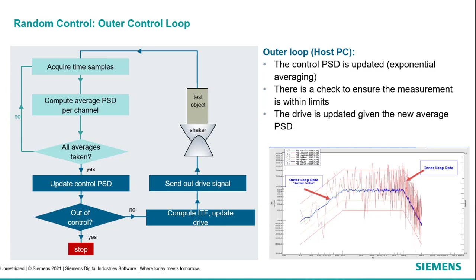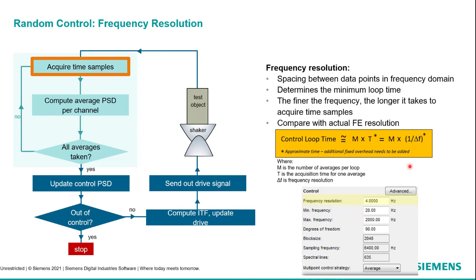Then we have another parameter that is part of the parameter settings, the frequency resolution, and this has a strong influence on the loop time. We have to have at least 1 over delta F for the time of one single average, and then we have a number of averages, and that's going to dictate our control loop time approximately. That's the minimum, but there's going to be some extra fixed overhead that contributes to the averaging time too.